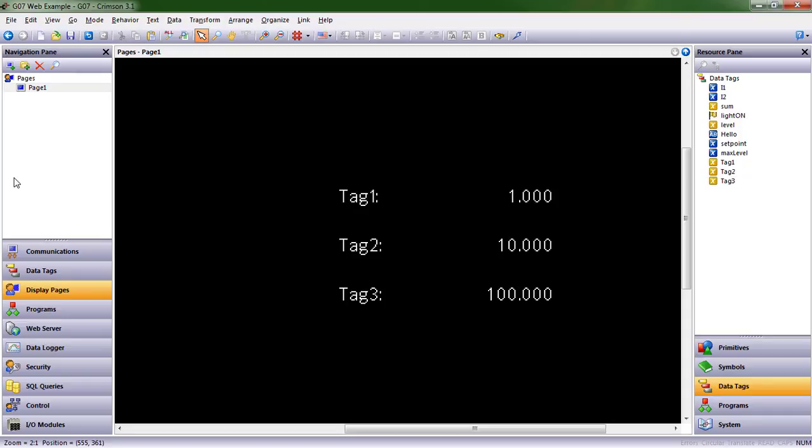Why do I bring this up? Let's say you have an analog input. Our analog inputs have 15-bit resolution, which means 32,768 values. However, on an analog input measuring a real-world signal, that may not be what we want to display on the screen. Maybe 0 to 32,767 is actually voltage from 0 to 10 volts. If I just do 0 to 10 without accommodating for the 32,768 steps, I'm not going to see anything interesting on the screen.